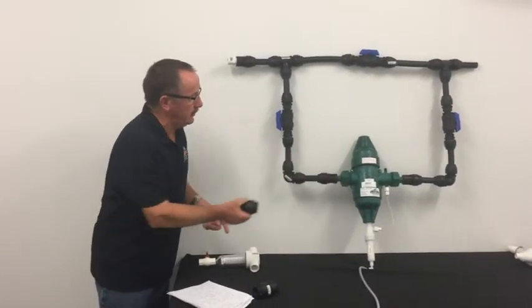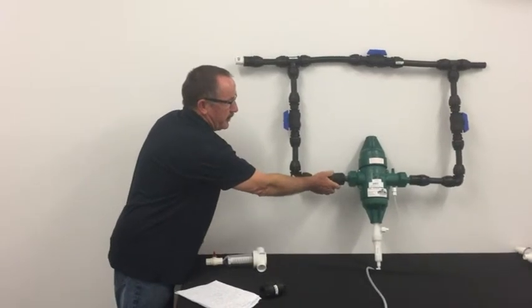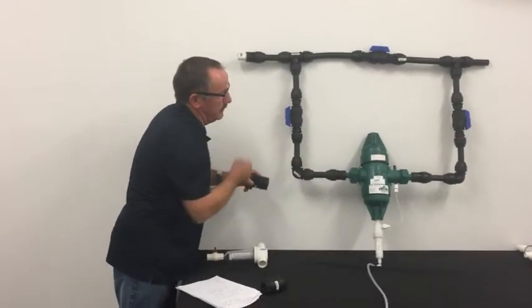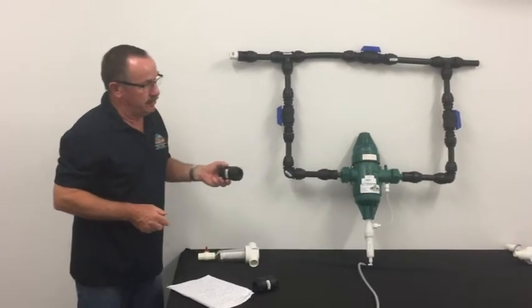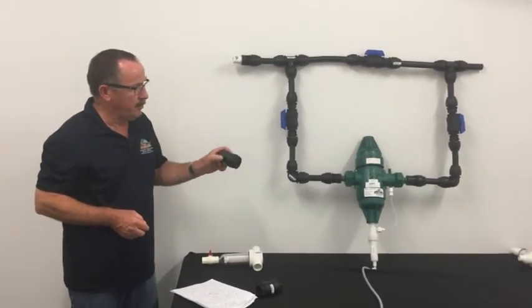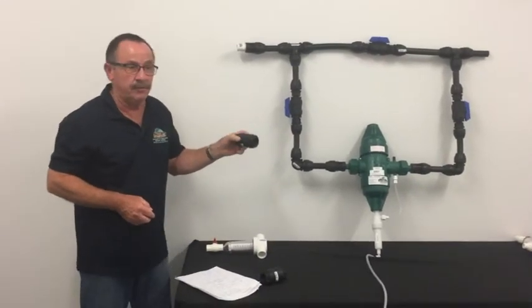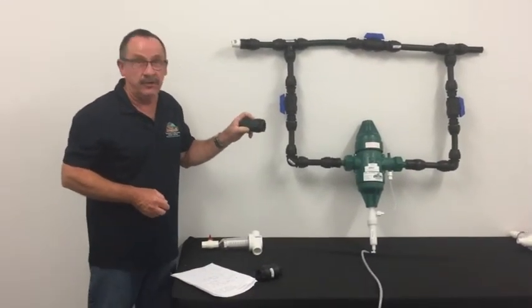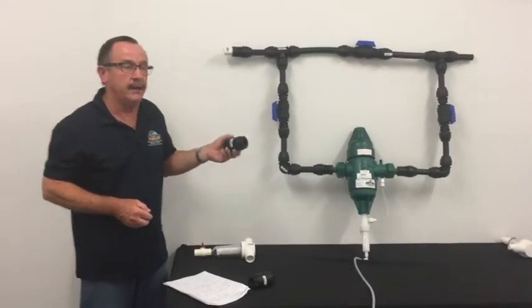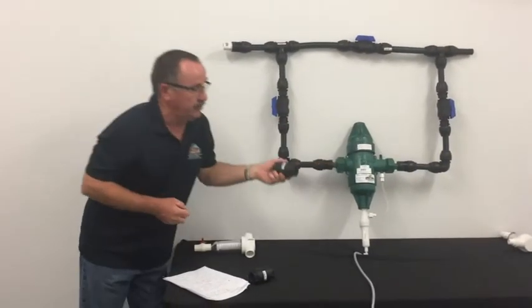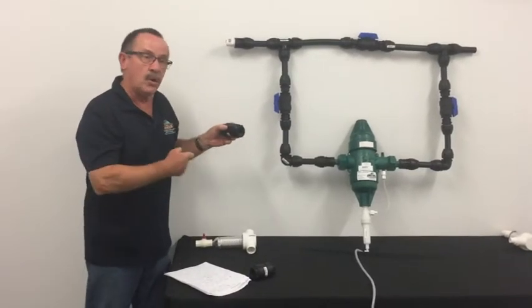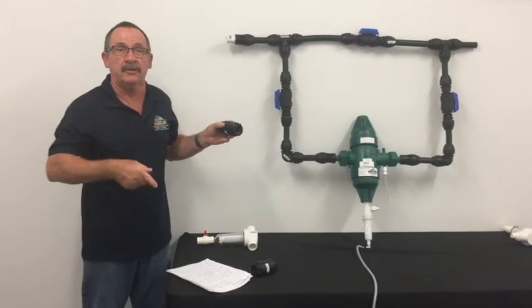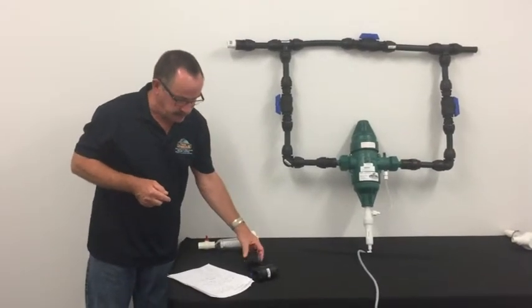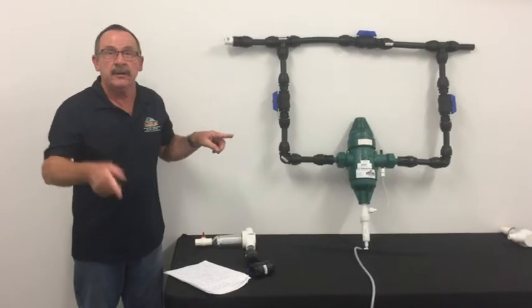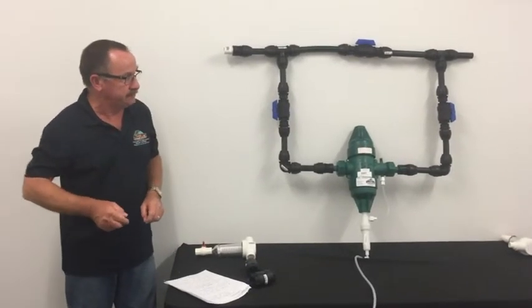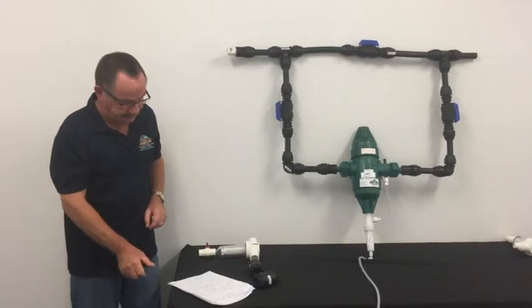If you had a gator like this, the right point would be just ahead of the gator so the water can't flow back into the system after it's been dosed. If you're dosing with a select doser, we'd recommend putting the non-return valve between the flow sensor and the injection point, on the other side. That stops water going the wrong way through the flow sensor and creating a situation where you're overdosing, because the flow sensor can create an inaccurate water flow message if it's running the wrong way.